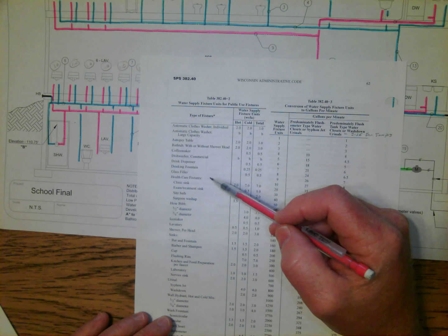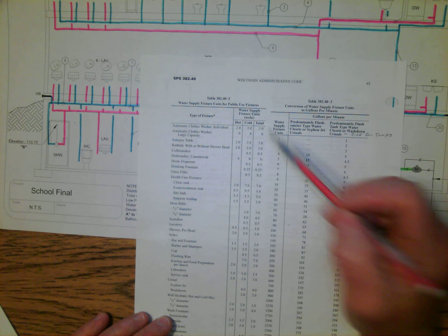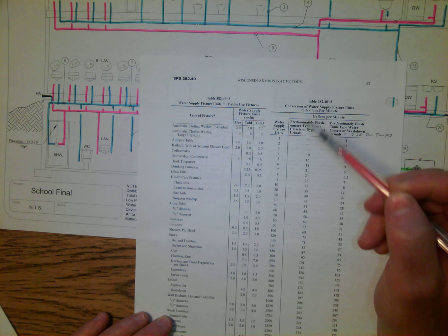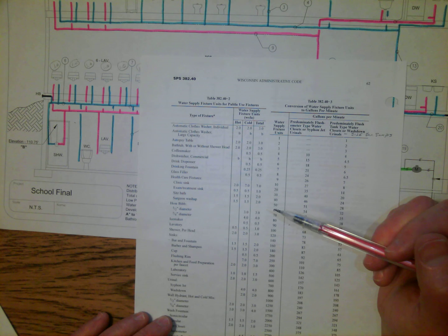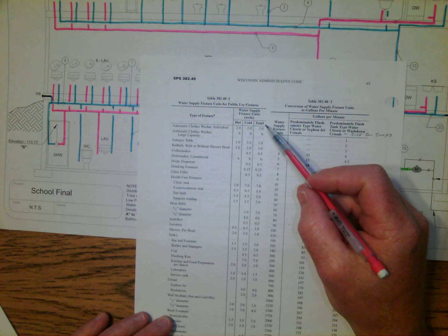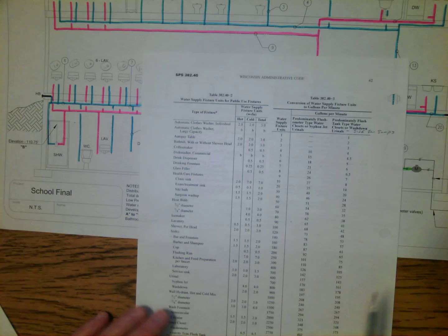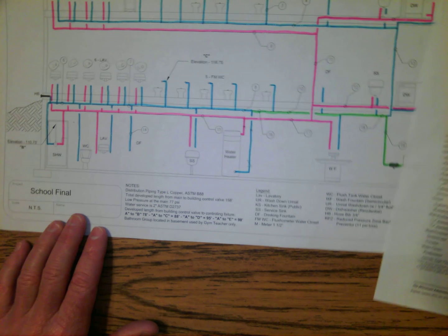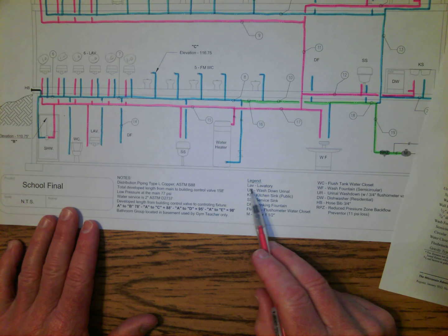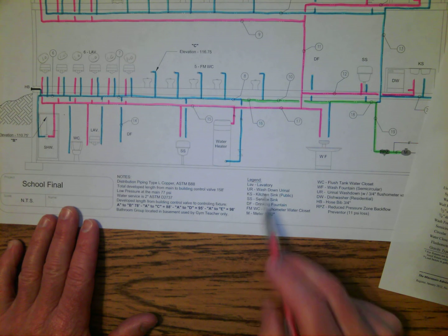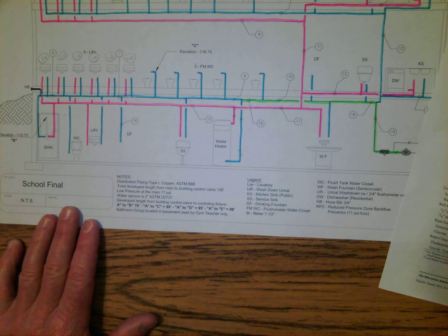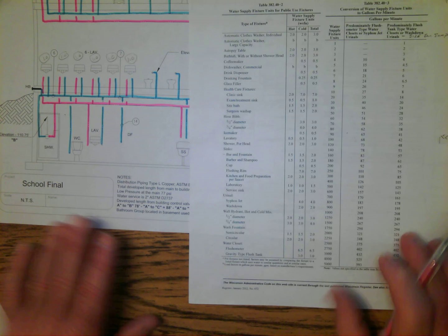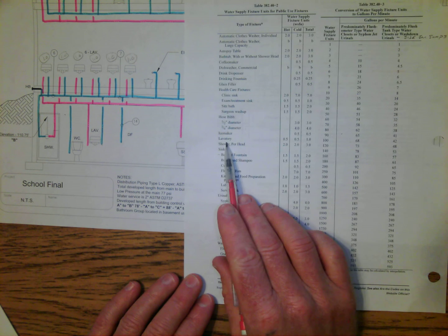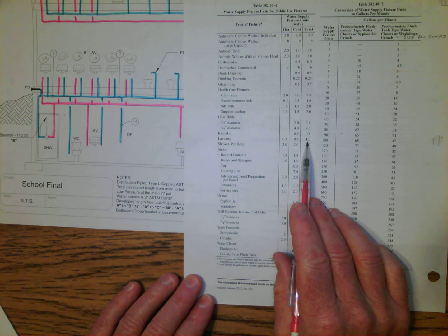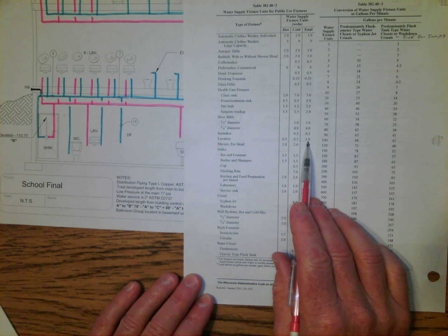Now that we have the right table, you can see that in that table, each one of the plumbing fixtures on it has a hot, cold, and total load that will be assigned to each one of the plumbing fixtures. For the time being, for this example, we're just going to assign the total loads. So at the bottom, we can see that LAV stands for lavatory sink, and a lavatory sink in a public building has a total load of 1 WSFU.